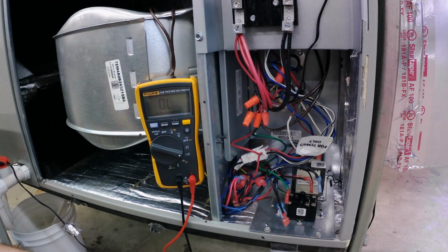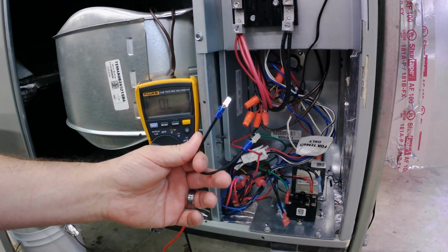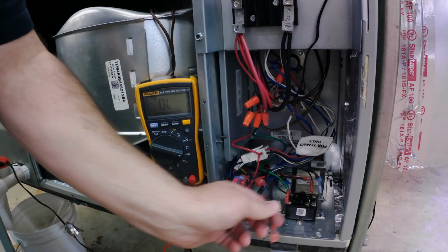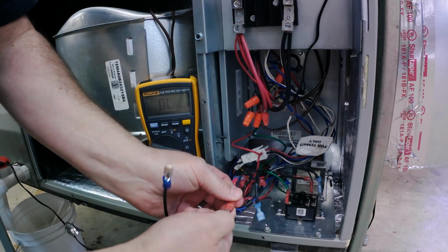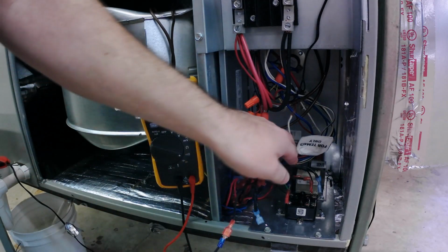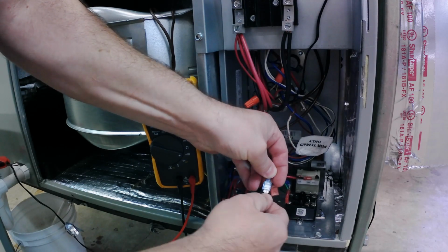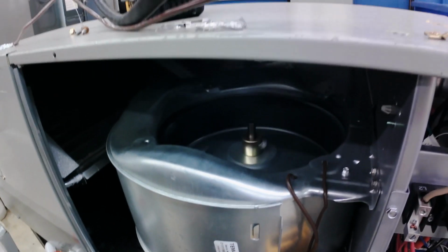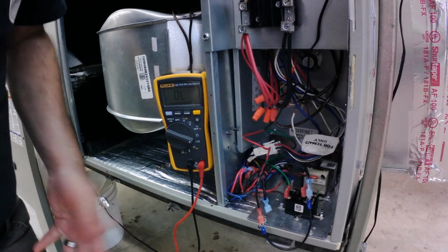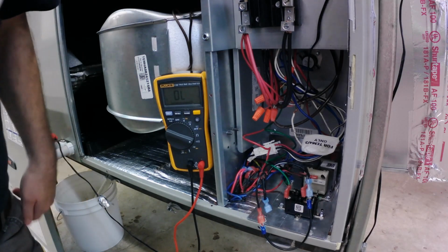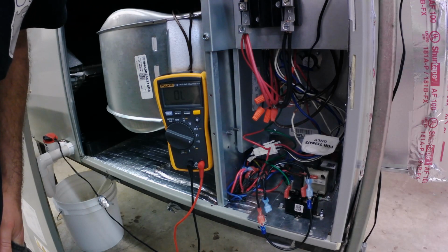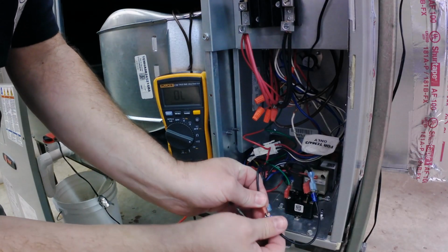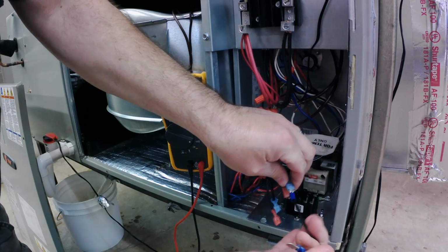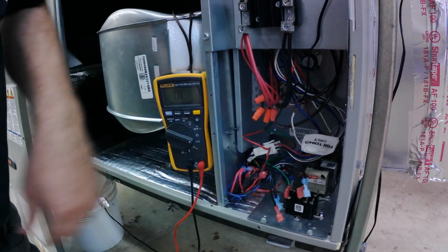What I usually do is take a real simple piece of wire with two male connections on it, and if you ever think that the relay is bad and you want to check the motor, you can easily put this little jumper in here and see if the motor starts working. You're essentially straight wiring the high voltage circuit for the motor to make sure that the motor is getting the proper power.